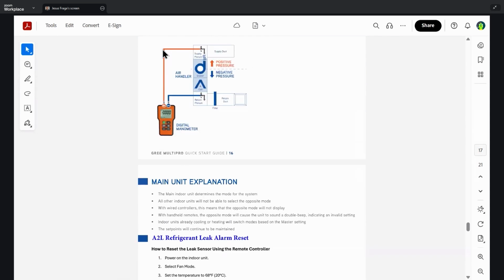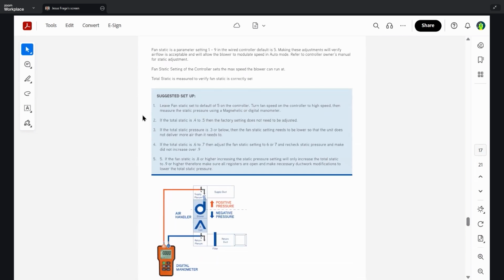And here's an illustration on how to actually take the static pressure. As I said, you'll take it across the air handler, so in the return plenum, the supply side, and depending on what value you get is how you'll follow the static pressure settings.